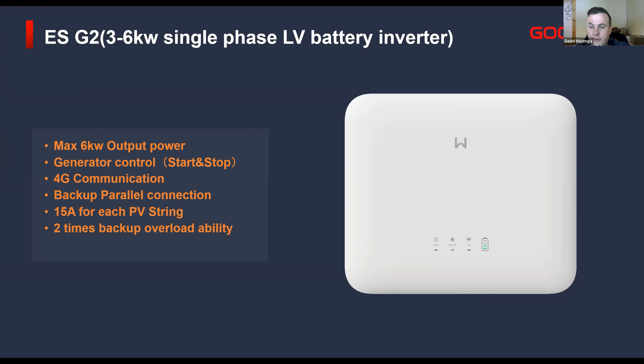There's also a lot of other extra control systems and improvements that will be coming with our device, like generator automatic start-stop, 4G communication for those remote areas where you're installing the devices remotely, and increased PV current. Because our new modules all have higher current inputs, we're increasing the current input for the inverter, and the backup overload capability of the inverter will also be increased. So we're looking at 2 times backup overload ability with the utility available, and at least 1.5 when it's unavailable, if you have sufficient battery capacity.